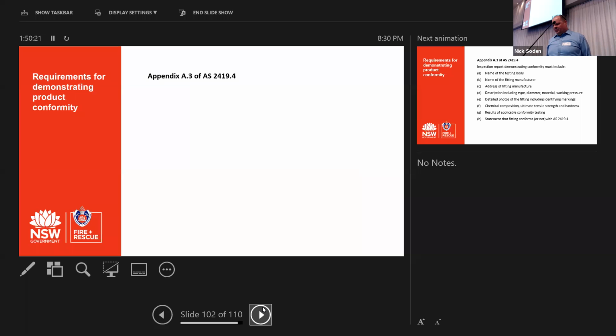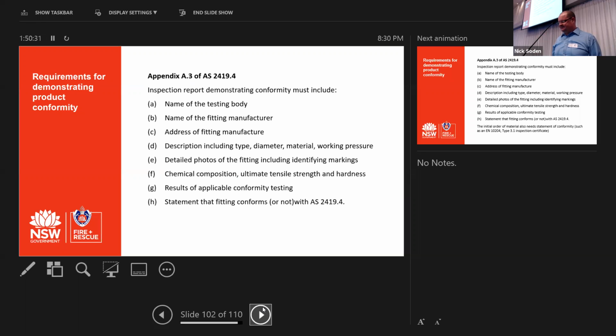Okay, this is the big one, requirements for demonstrating product conformity. So appendix A.3 of part 4 basically says this. The required inspection report demonstrating conformity must include the name of the testing body, the name of the fitting manufacturer, the address of the fitting manufacturer, because sometimes they do change the place of manufacture. Description, including type, diameter, materials, working pressures. This is when they're making more than one product, which most of them do anyway.